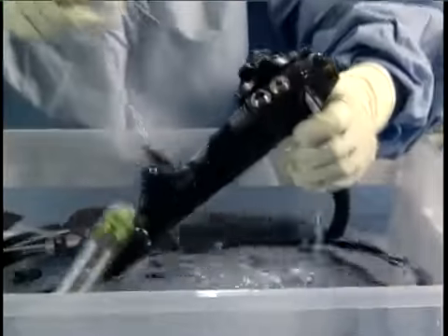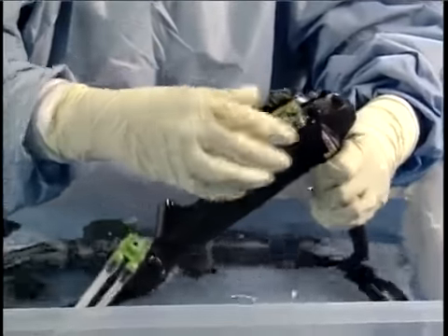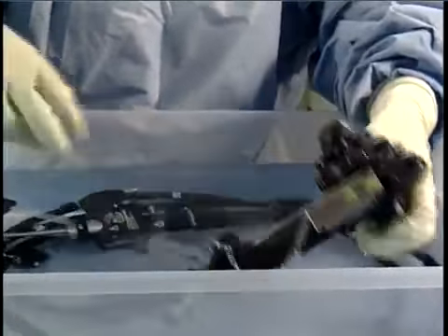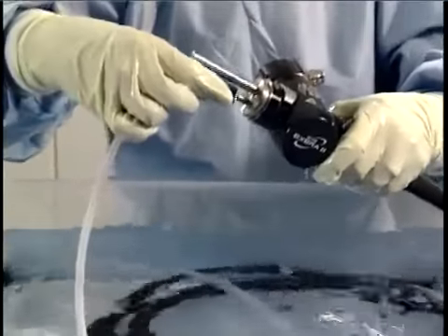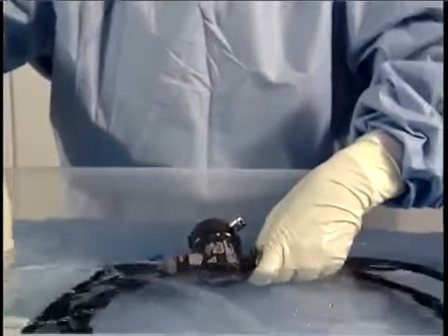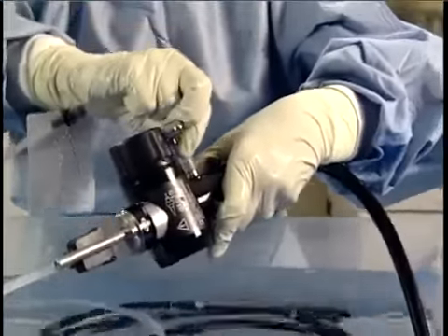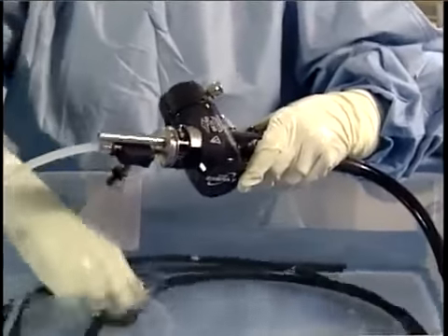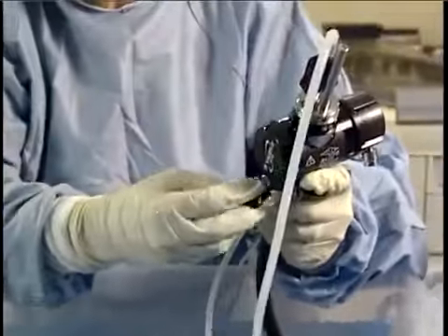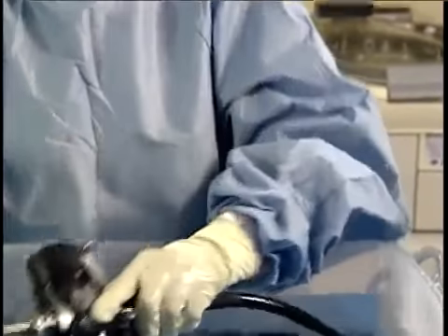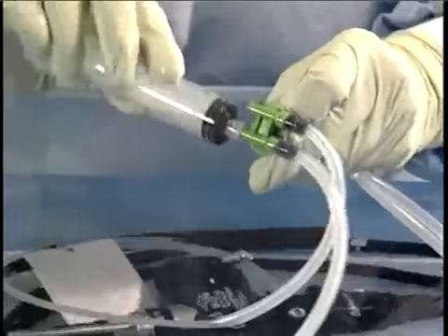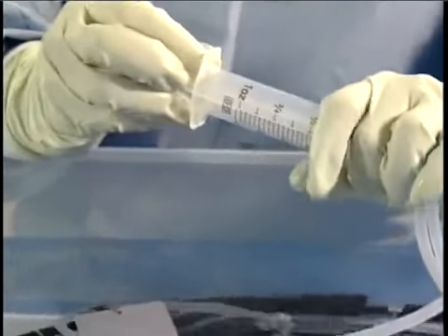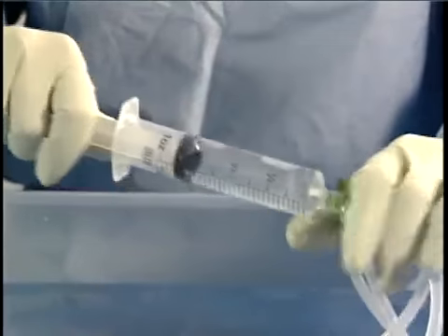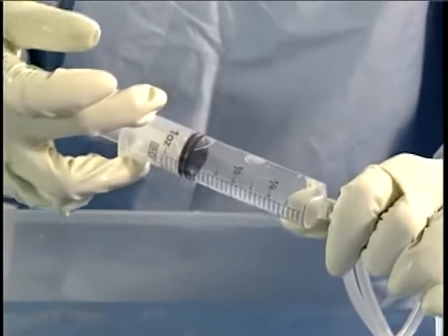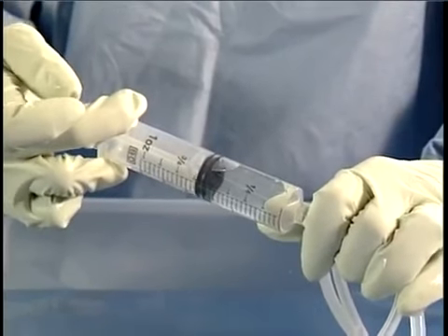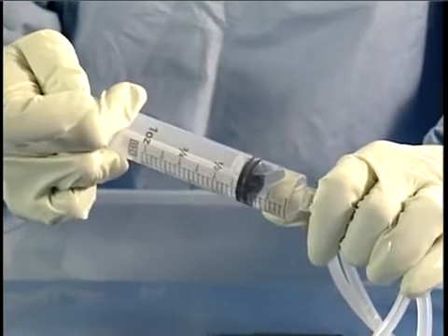To flush the air-water channel, attach the channel plug to the valve housings and instrument port. Attach the injection tube to the air pipe, the suction port, and the water and air connectors. Next, attach a 30 cc syringe to the air-water channel port of the injection tube. With the intake filter immersed in detergent, use the syringe to flush 90 cc's of detergent solution through the air-water channels.